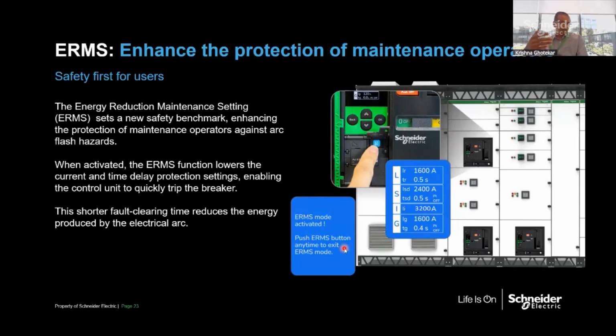Can this be done wirelessly with some other things? Yes, we can think of it. There is an option for that also, but we have still kept it as manual human intervention, because this protection is required whenever an operator is walking into or out of the electrical room. So, entering and exit. Since the human presence will be there, we keep it that he has to activate or deactivate. But for that, you don't have to add on a hardware switch or anything else. It's a simple button on the trip unit.